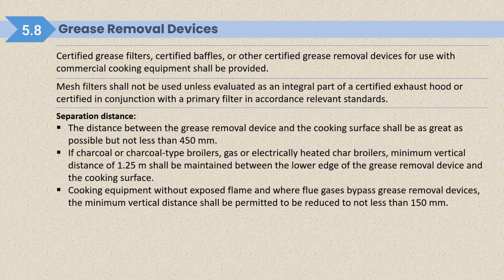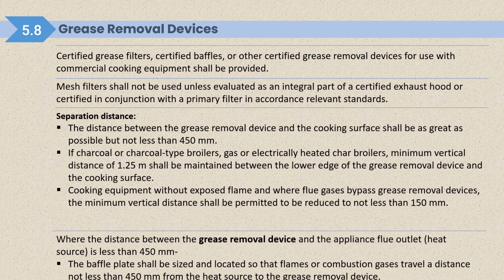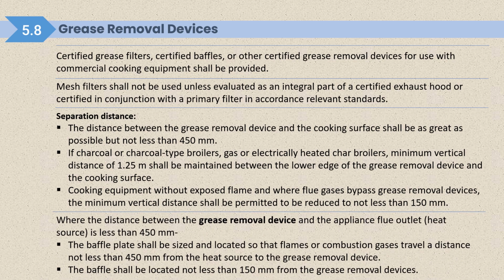Cooking equipment without exposed flame, and where flue gases bypass grease removal devices, the minimum vertical distance shall be permitted to be reduced to not less than 150 mm. Where the distance between the grease removal device and the appliance flue outlet heat source is less than 450 mm, suppose we are not able to maintain the distance of 450 mm, in that case the baffle plate shall be sized and located so that flames or combustion gases travel a distance not less than 450 mm from the heat source to the grease removal device. The baffle shall be located no less than 150 mm from the grease removal devices. So there should be the provision of baffle plate if we are not able to maintain the gap of 450 mm.